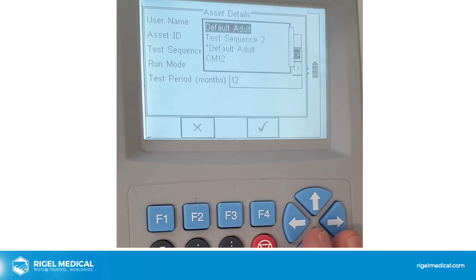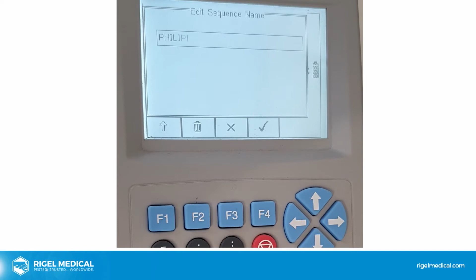So if I go to automatic mode, there'll be a preset default test sequence, and some custom test sequences that I've set up previously. The way you do this is you go to F4, set up test sequences. The easiest way is to copy the default adult test sequence rather than creating one from scratch. I'm going to call this one Philips, custom to this monitor.